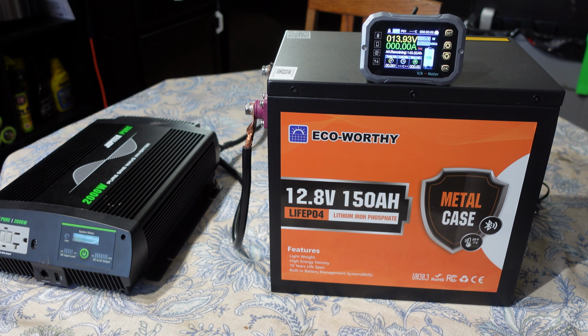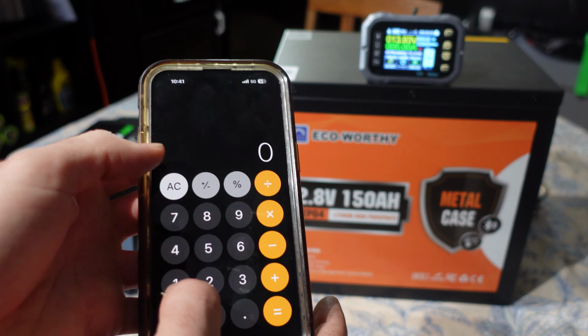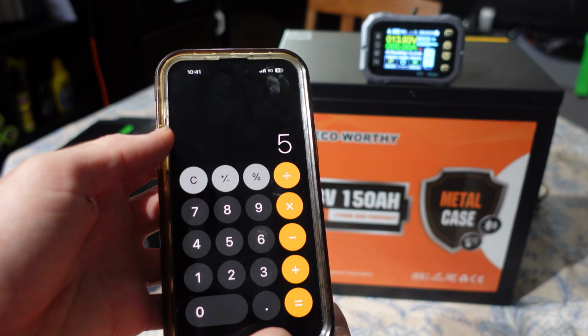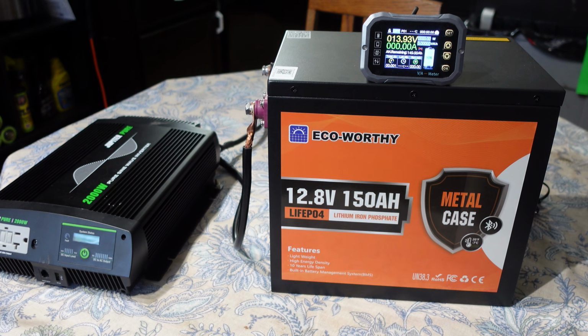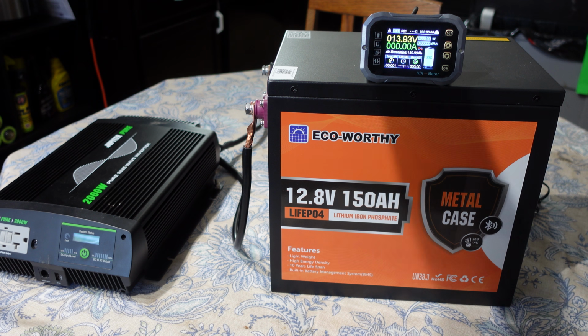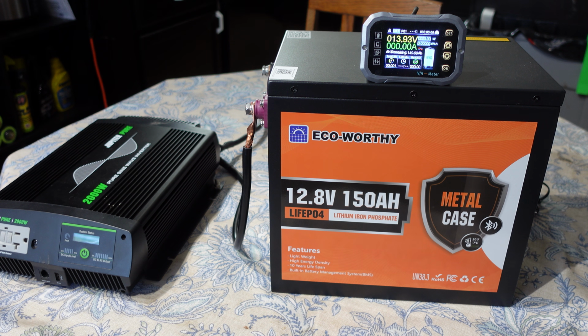Now we're gonna put a 0.2C load on the battery using my Harbor Freight pure sine wave inverter, and that's gonna be powering the charge inverter to charge the 48 volt power system, just like we always do. So we're going to put approximately a 30 amp load, and the way I got that is 150 divided by 5. That's 30 amps, so that's gonna be a 0.2C load on the battery. So we're gonna go ahead and get that going, and it's 30 amps on the DC side. Once I have the current stabilized, we're gonna start the test.